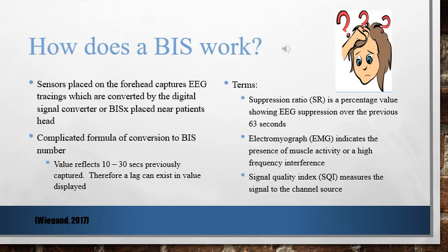Okay, and it's a really complicated formula, and it converts it and it throws that number up there on the screen for us. But the one thing you should realize is that there's a 10 to 30 second delay between what the patient is actually doing and that number we see on the monitor. There's a lag because of that complicated conversion that has to take place.